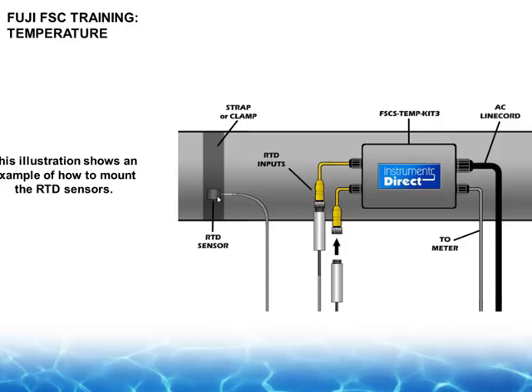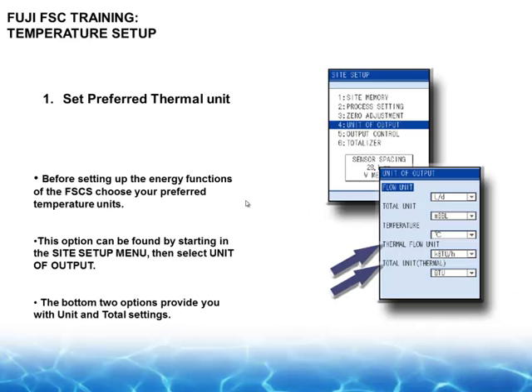These transducers that come from us, the temperature sensors, are calibrated for plug and play, and they're better than 1% temperature differential. The problem is if you use hokey temperature monitoring, if you have bad temperature differential monitoring, you've just screwed up the whole BTU calculation. You're off a couple degrees, you can be off 10% or more on your BTU calculation, and so the whole thing's done in vain. So, very precision use of our package that we have there.